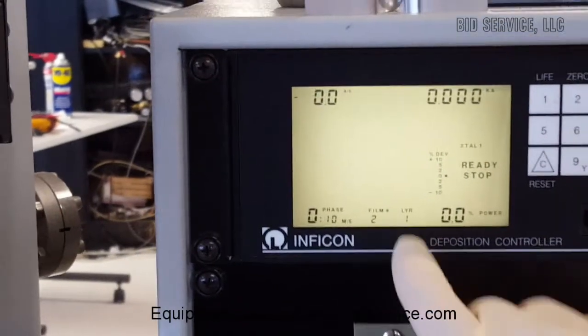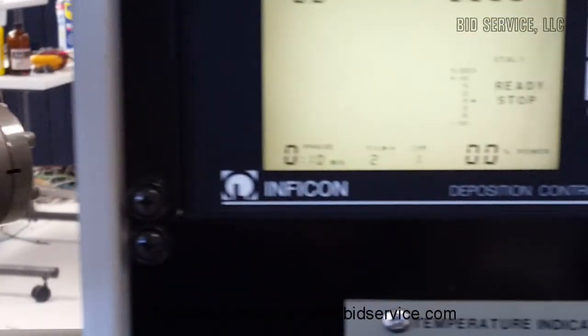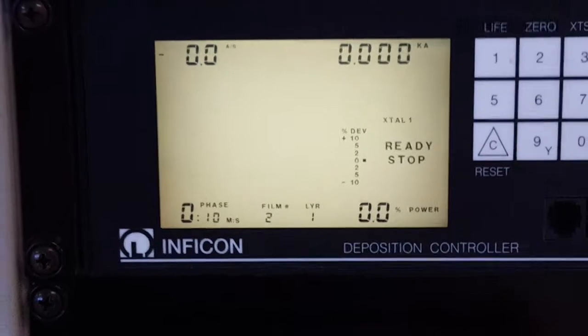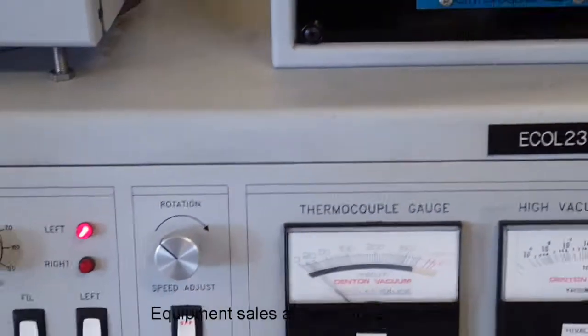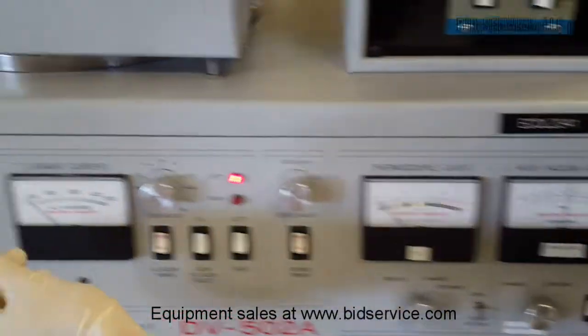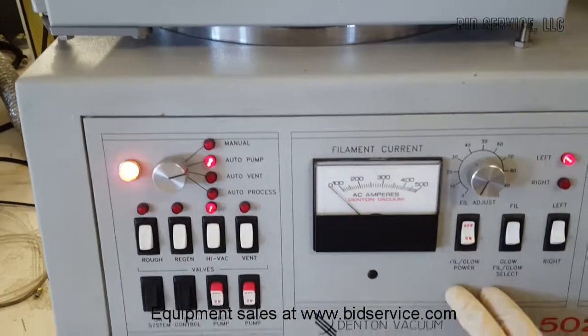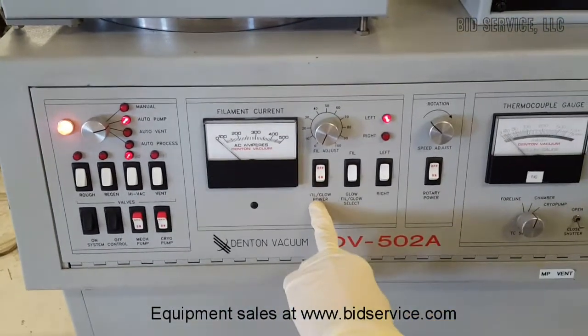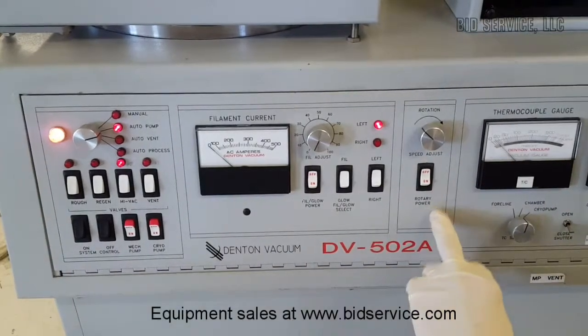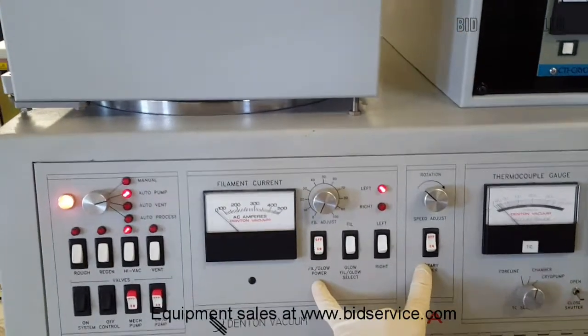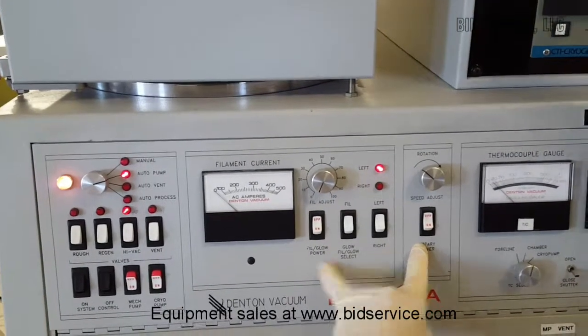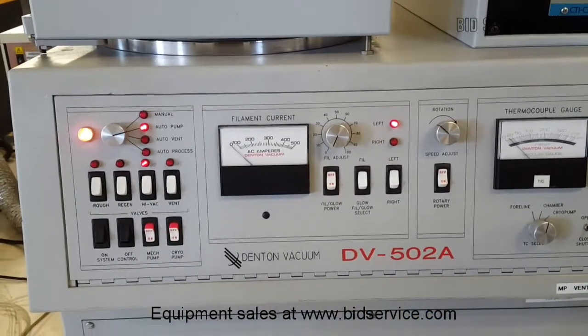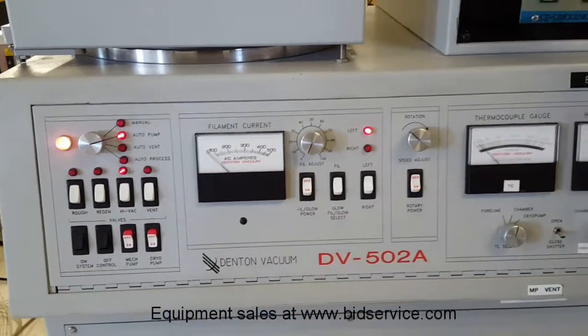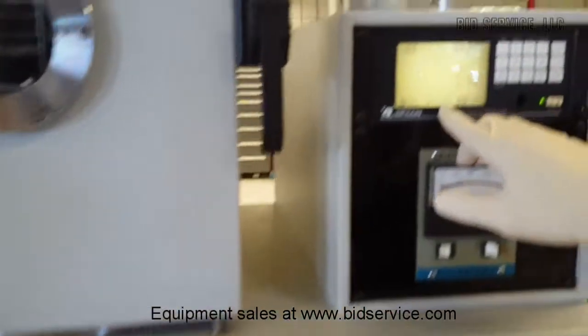So you can see film number 2, layer 1, it's in ready, stop mode. So at this point you can allow it to pump down. Like I said, it should go into the 7 range. We're pretty low in the 6 range now, so I'm just going to flip it over to auto process. In auto process mode, you don't have to turn on your filament power or your rotary power. It'll turn on automatically, and your shutters again are controlled by the deposition controller. So all we need to do at this point, we're going to put down film number 2 at layer 1. So we'll go ahead and switch this over to auto process.